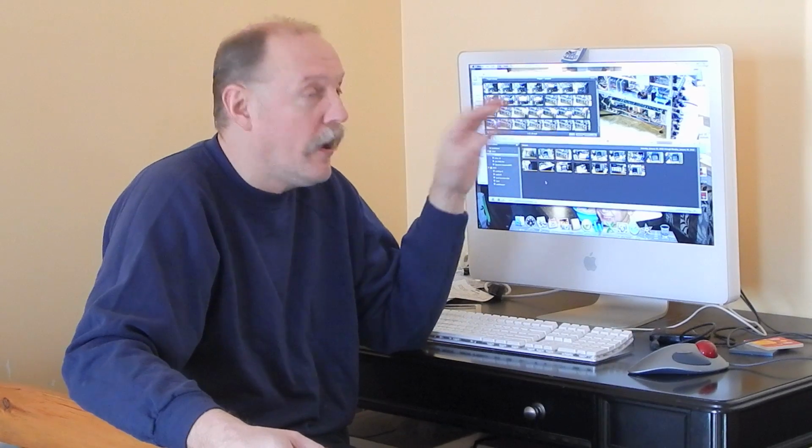And I liked this scope so much, cutting my teeth on it, that when I opened my own shop, I bought one. And then I didn't have that scope very long. This is the SC61. It was a 60 megahertz oscilloscope, but they always told us it was usable to 100. So I guess the response drops off as you get closer to 100 megahertz. Up to 60 megahertz, it's pretty rock solid.